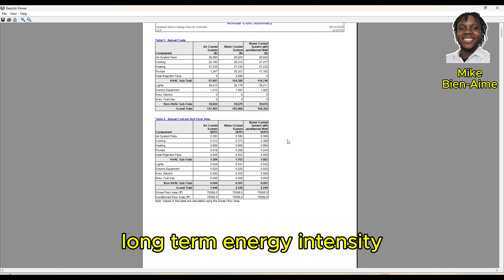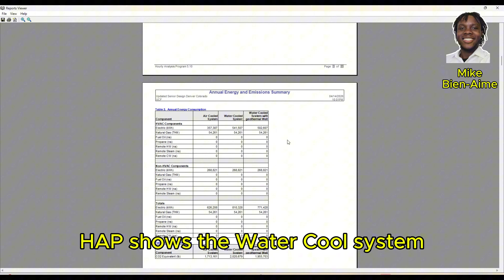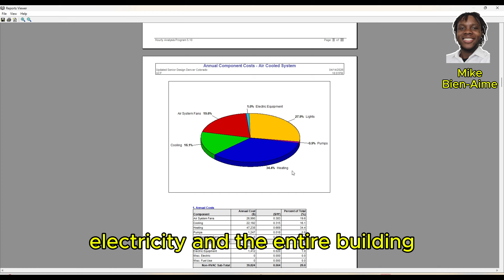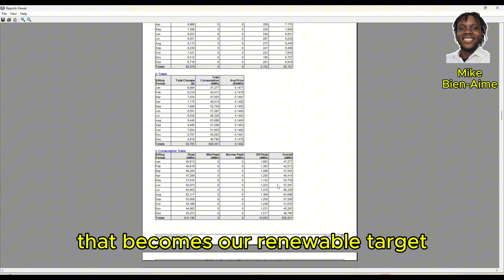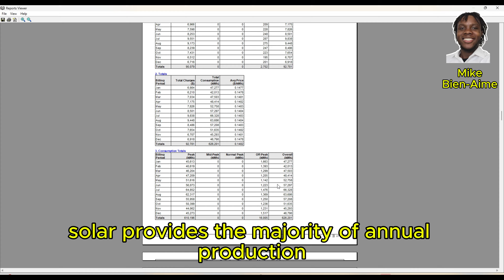From a financial perspective, this matters because the water-cooled system delivers lower long-term energy intensity, which directly reduces the size and cost of the renewable system required to reach net zero. HAP shows the water-cooled system uses about 541,000 kilowatt-hours of HVAC electricity, and the entire building totals about 810,000 kilowatt-hours per year. That becomes our renewable target. We then size a hybrid solar and wind system to offset that load. Solar provides the majority of annual production, while wind stabilizes performance during nights and winters.